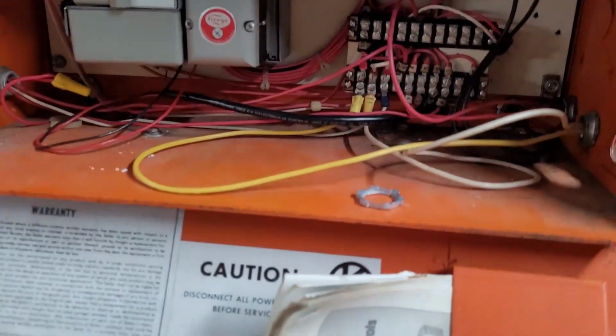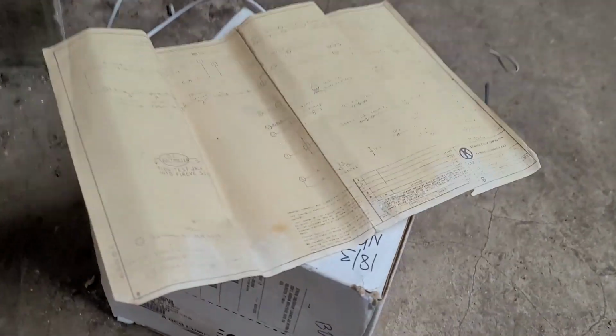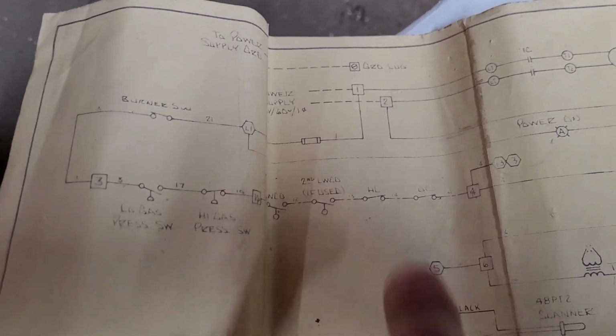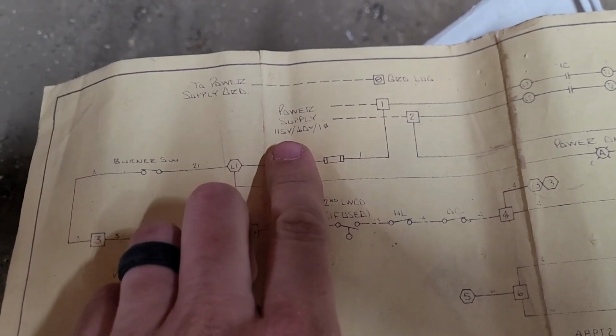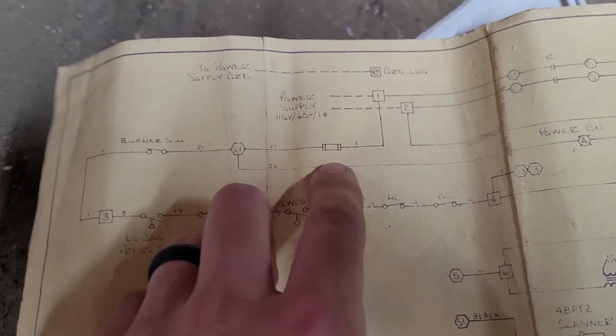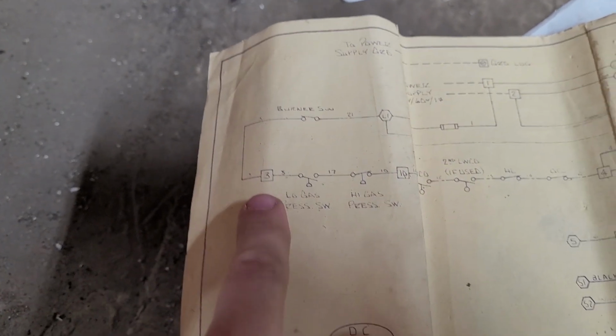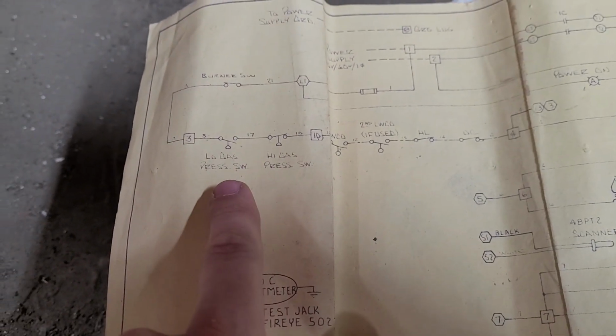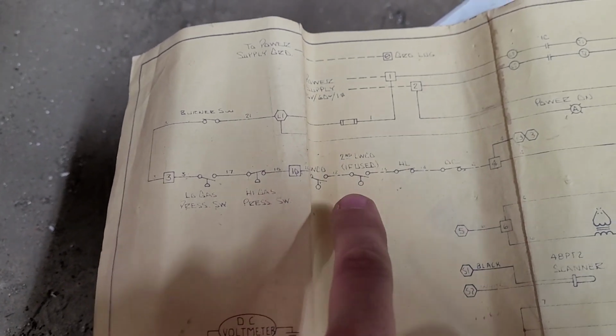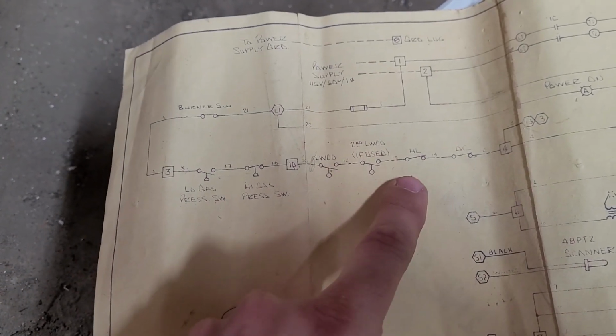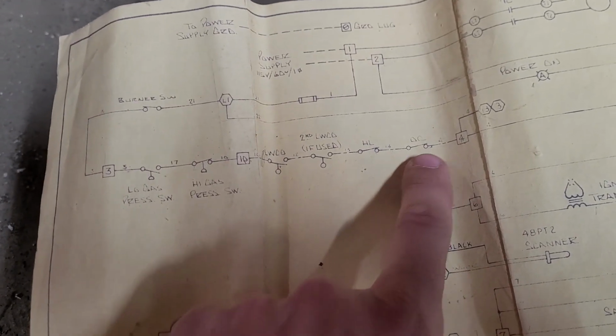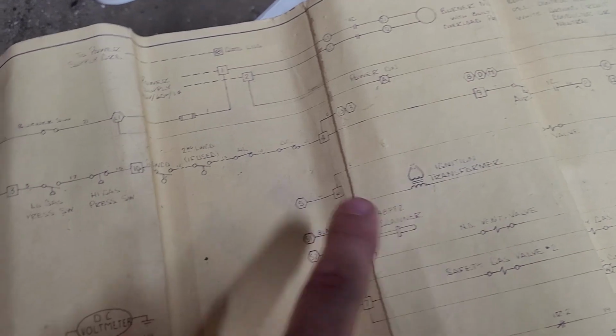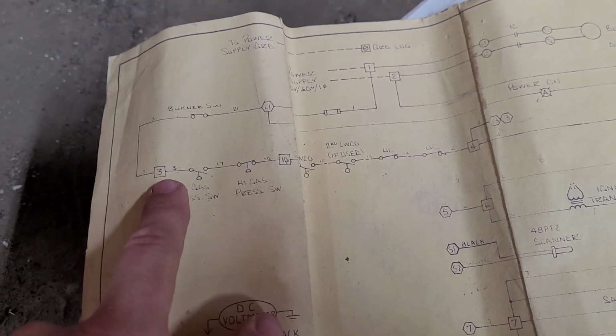So we're looking for a terminal where we can tie our relay in. They were nice enough to make this diagram for us. So what we've got is 120 volts coming in. See, there's 115. So your 120 volt coming in to a fuse, and then it goes to the burner switch, which is here. After that, it goes to terminal 3, and then it goes through all the safeties. Gas pressure safety, high and low gas safety, low water cutout, high level cutout, and some other things. So I'm just going to break it right before it gets to terminal 3.